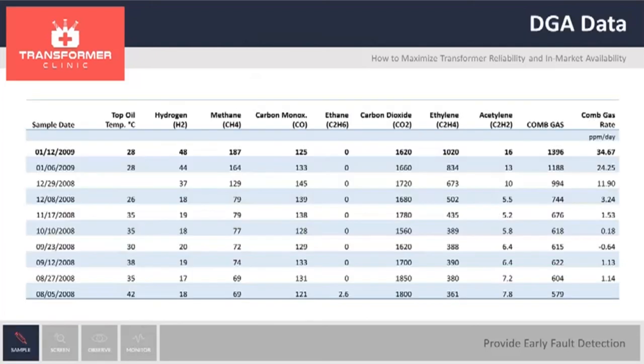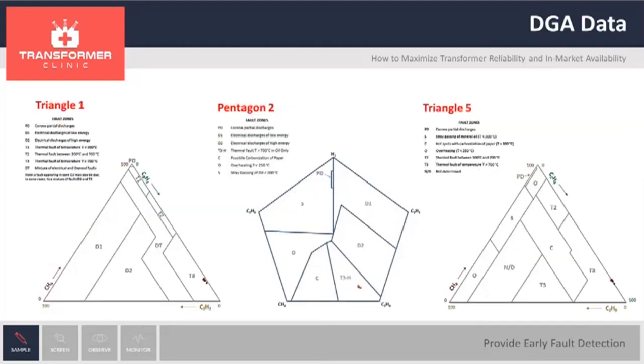When looking at the DGA data, you can see the evolution. Ethylene, when we started monitoring, was at 361 parts per million. By the end of monitoring, we were at 1,020 parts per million. The gassing rate at the beginning was 1.14 parts per million per day. The gassing rate at the end was 34.67 parts per million per day. So it is clear that the fault was getting worse and evolving. Looking at the DGA data, the diagnoses were: with Duval Triangle 1, we have a high-temperature fault; with Duval Triangle 5, we have a high-temperature fault; and with Pentagon 2, we have a high-temperature fault in the oil — the same diagnosis from all of them.